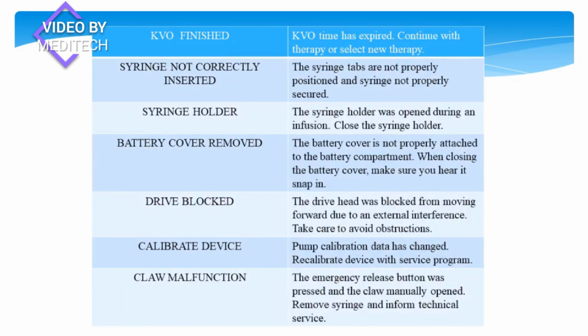Next, KVO finished. KVO time has expired. Continue with therapy or select new therapy. Syringe not correctly inserted. The syringe tabs are not properly positioned and the syringe is not properly secured. Syringe holder. The syringe holder was opened during an infusion. Close the syringe holder. Battery cover removed. The battery cover is not properly attached to the battery compartment. When closing the battery cover, make sure you hear it snapping.